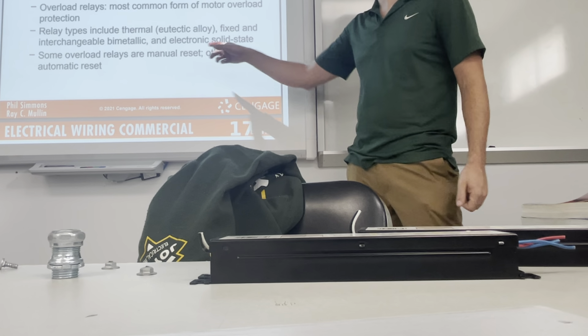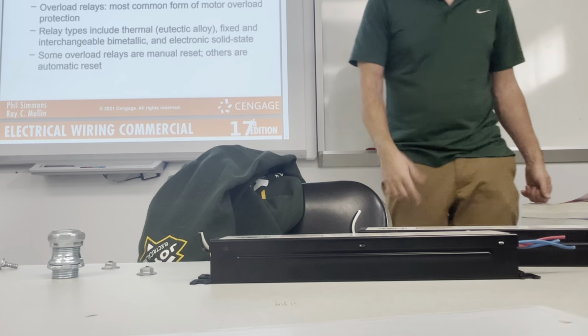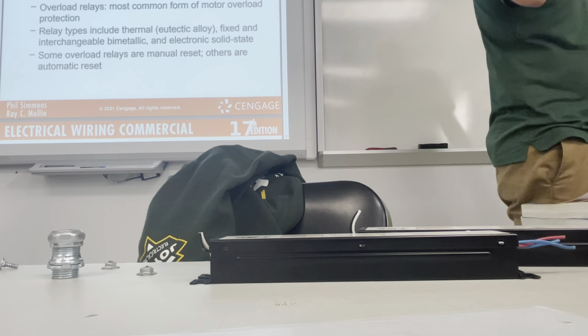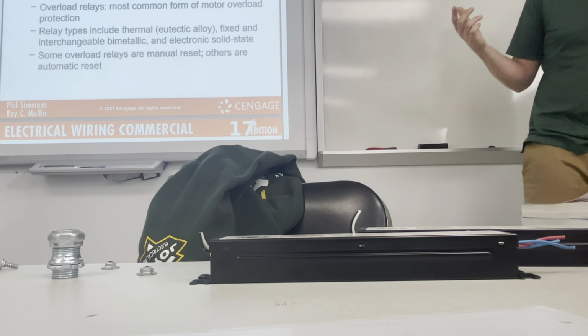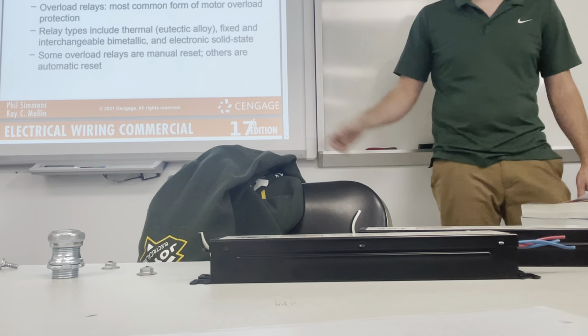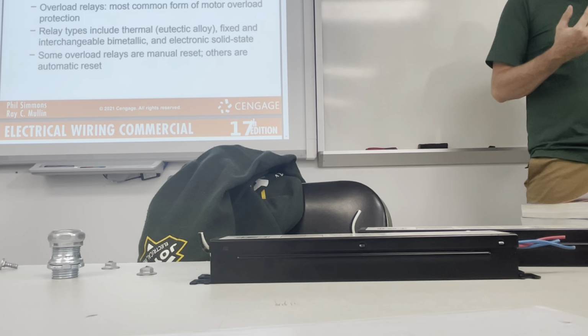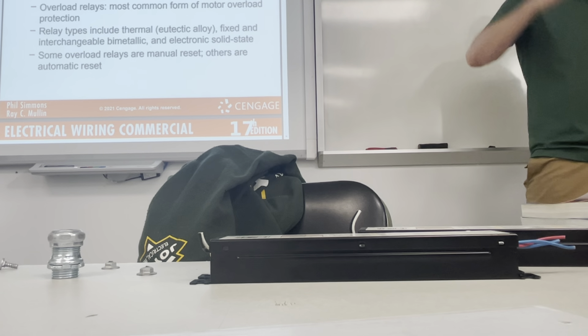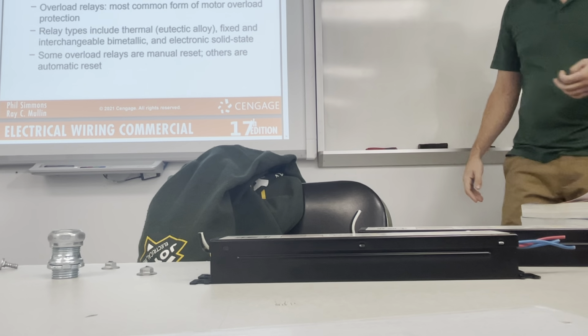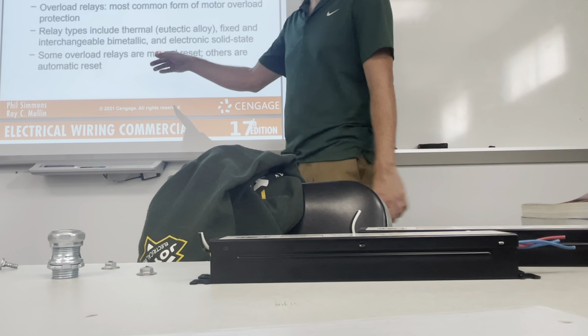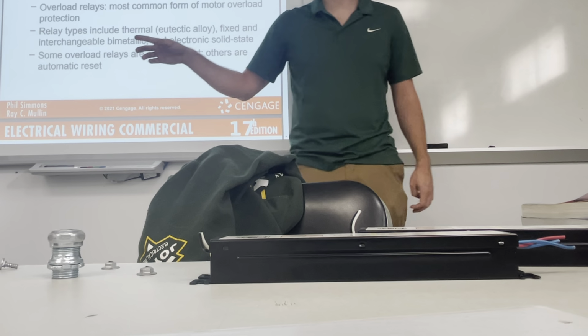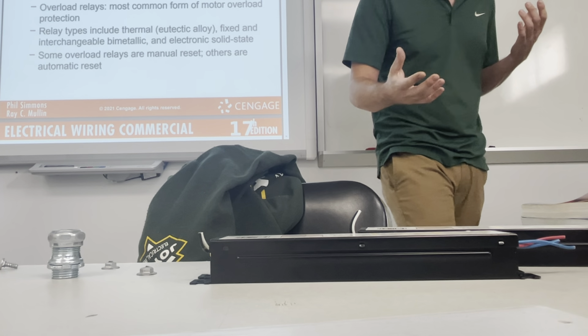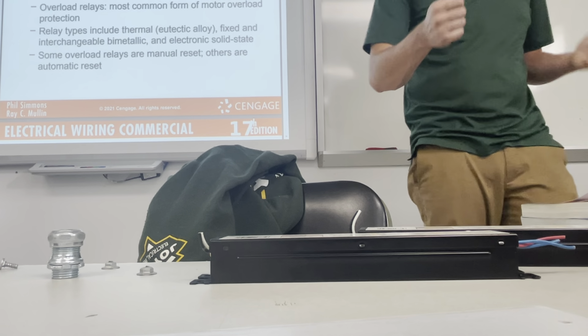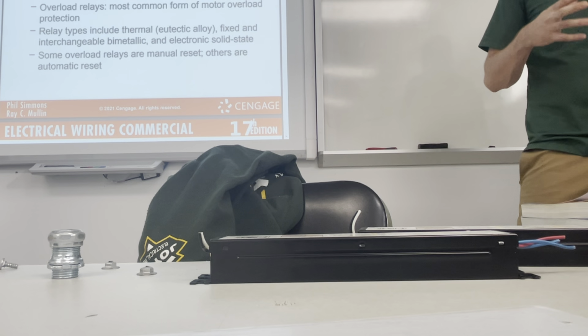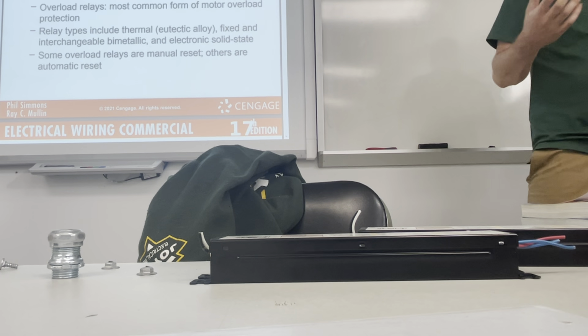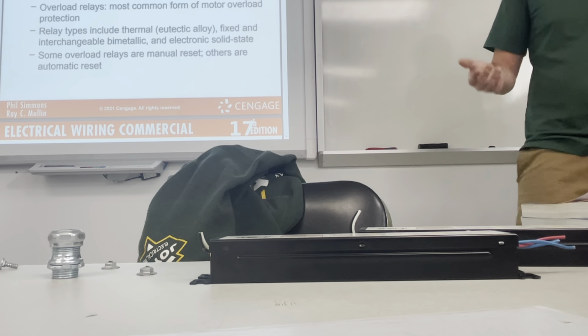Now, when they say some are manual reset and others are automatic, the manuals, obviously, you have to go and hit the reset button and then it'll turn right back on. The automatic resets wait until they cool, go back into their normal position, and then they'll fire again. Manuals are good if it's going to be in a factory, where somebody's going to be around that machinery. That machinery turning back on randomly might hurt somebody. That's when you're going to want a manual.